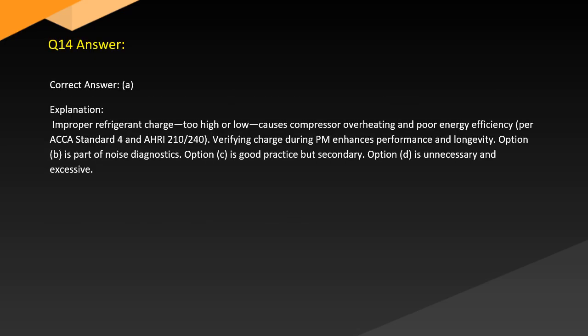Answer. Correct answer: A. Explanation. Improper refrigerant charge, too high or low, causes compressor overheating and poor energy efficiency per ACCA Standard 4 and AHRI 210/240. Verifying charge during PM enhances performance and longevity. Option B is part of noise diagnostics. Option C is good practice but secondary. Option D is unnecessary and excessive.